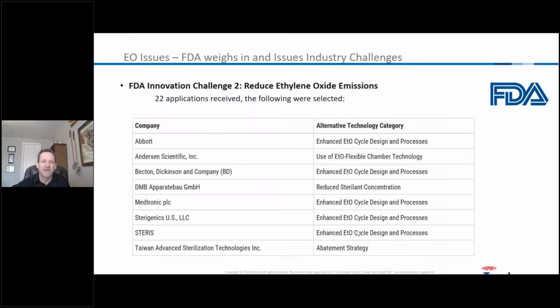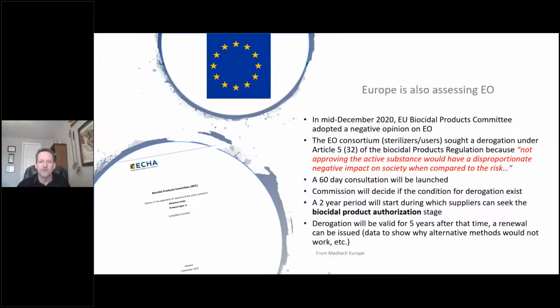So the second part of that challenge was, okay, what can we do to reduce ethylene oxide emissions? If you look at this list here, many of these are dealing with looking at the EO process, optimizing it, enhancing it. In a lot of cases, what they're doing is minimizing the amount of gas that's used, cutting the gas concentration in half. If you cut that in half, then immediately you have just half the amount of emissions there alone. Other people are looking at only running it with a full chamber, so you're really maximizing the ethylene oxide that you are using. So again, this was a big US issue, but it's also kind of spread to Europe now.